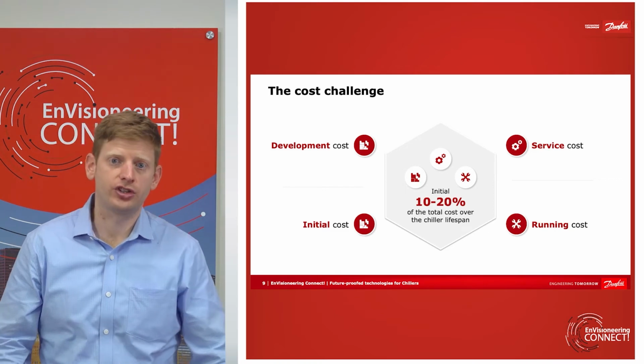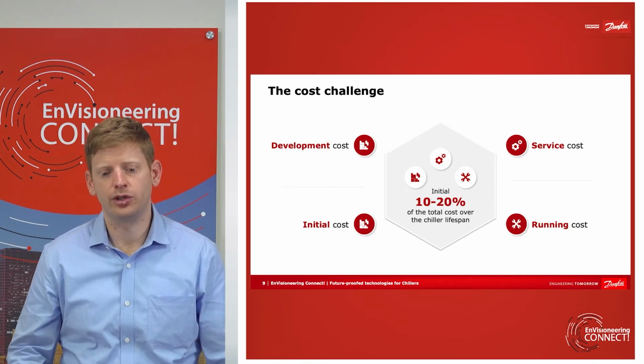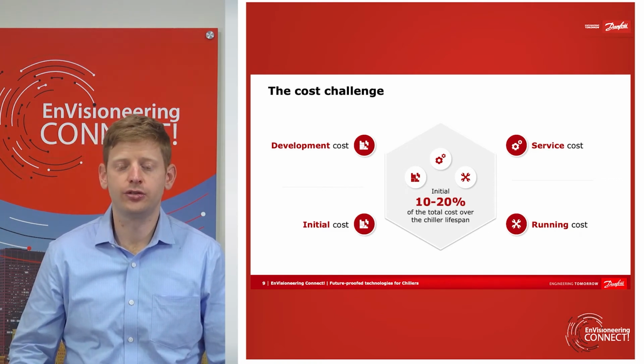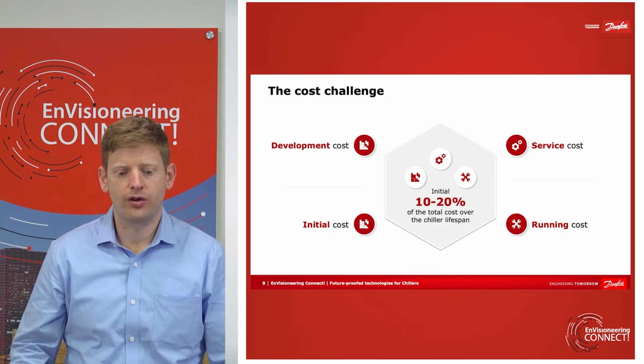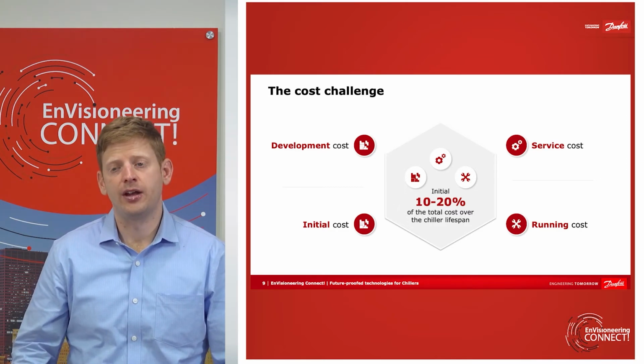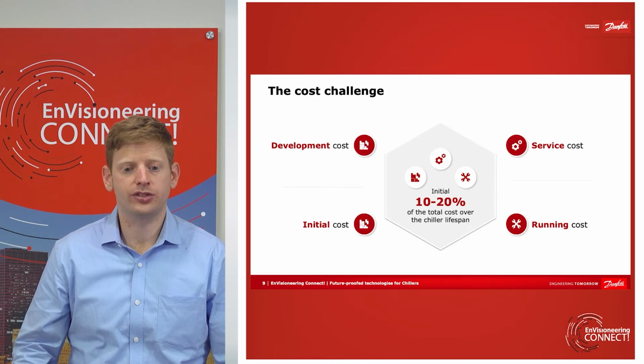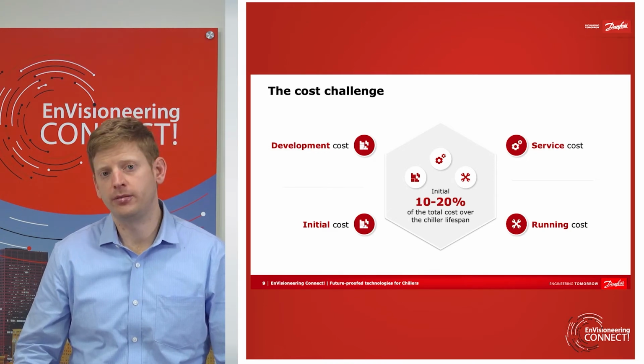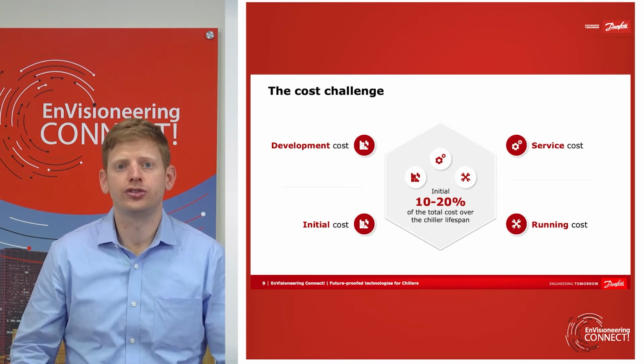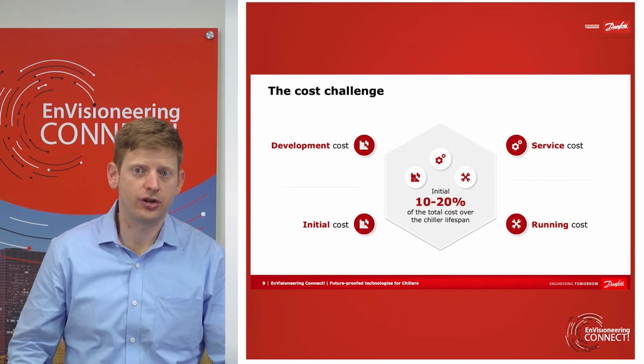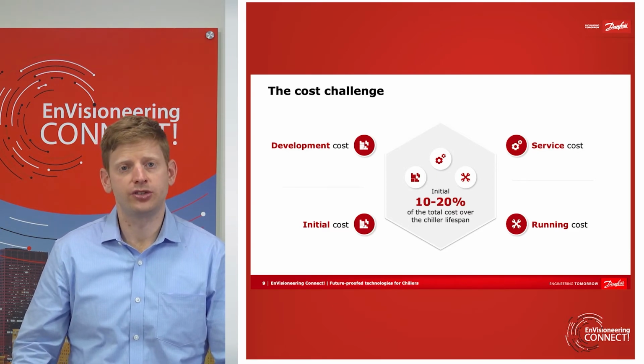When it comes to servicing a chiller long term, it's important to look at the refrigerants being used. Over time, current refrigerants are going to be phased down, and as they get phased down, their costs will probably go up and their availability might be harder to come by. So building owners will actually have to consider what refrigerant is being used, because it'll have an impact on their long-term costs.